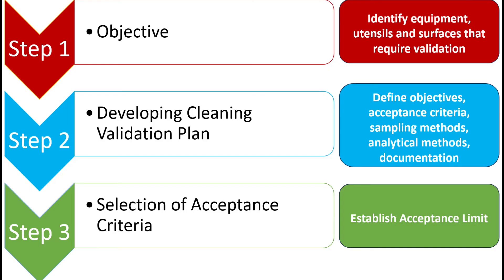Step two is to develop the cleaning validation plan, which is also called the validation protocol. The validation protocol includes defined objectives, acceptance criteria, sampling methods, analytical methods, and documentation of everything. Step three is the selection of acceptance criteria, to ensure that the cleaning process can perform whatever it proposes. For example, not more than 10 ppm of any product will appear in another product — this is an example of an acceptance criteria.